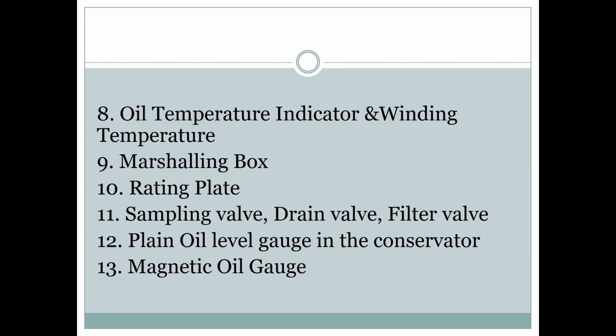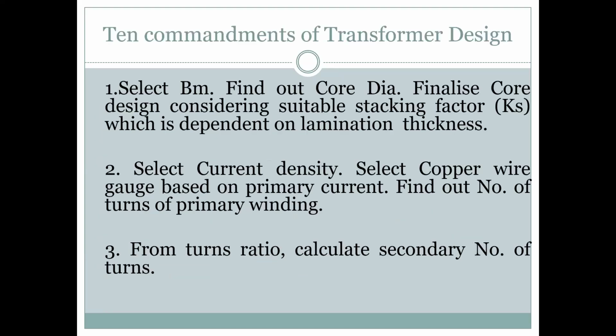We can see how much oil is there, because during summer it goes up and in winter it comes down because of the breathing of the transformer, the pressure in the transformer. A lot of things are there. There is a magnetic oil level gauge also, additional protection, so that if the level goes down suddenly, it gives you the alarm.